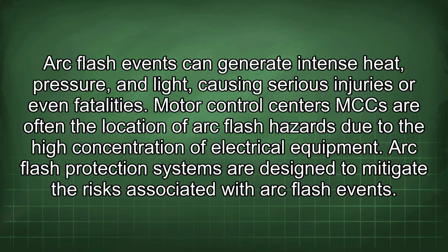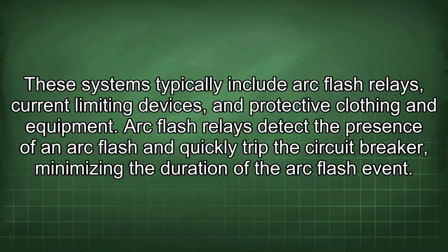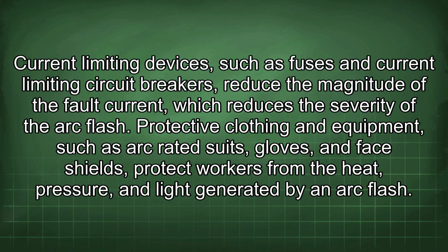Arc flash protection systems are designed to mitigate the risks associated with arc flash events. These systems typically include arc flash relays, current limiting devices, and protective clothing and equipment. Arc flash relays detect the presence of an arc flash and quickly trip the circuit breaker, minimizing the duration of the arc flash event. Current limiting devices, such as fuses and current limiting circuit breakers, reduce the magnitude of the fault current, which reduces the severity of the arc flash.